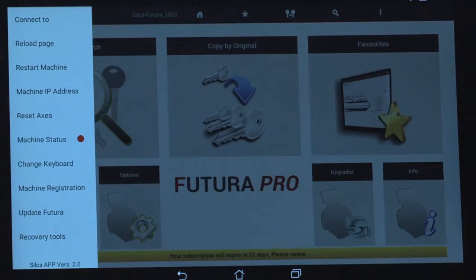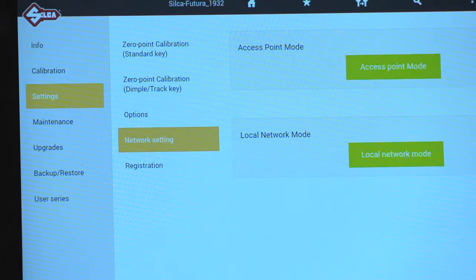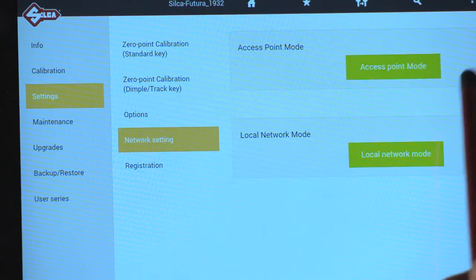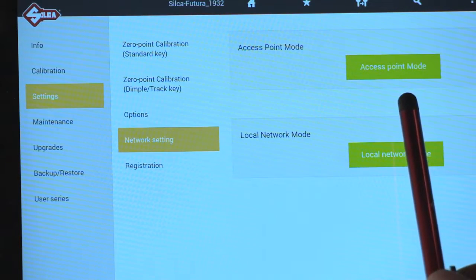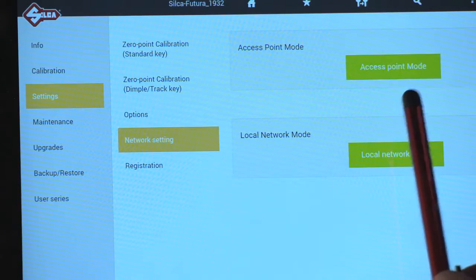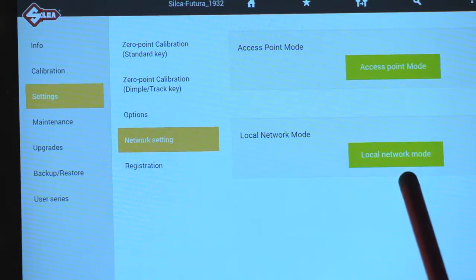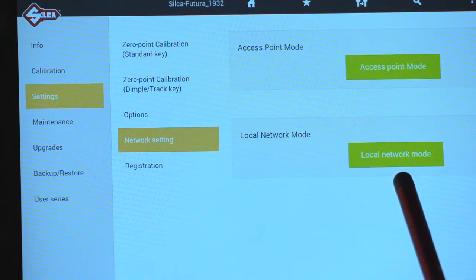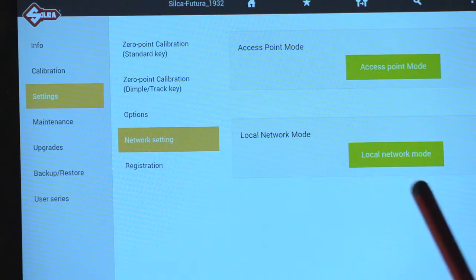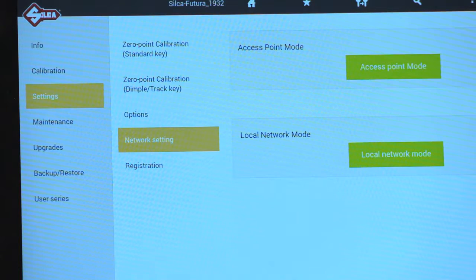Once the connection is made, it can take several minutes for the software to download from the machine to the tablet. In access point mode, the tablet connects directly to the machine via a Wi-Fi signal generated by the machine. In local network mode, the Futura Pro and the tablet are connected through a Wi-Fi router or cabled network. This mode allows internet access with the tablet and is used for updating the software. Refer to the software operating manual for additional information.